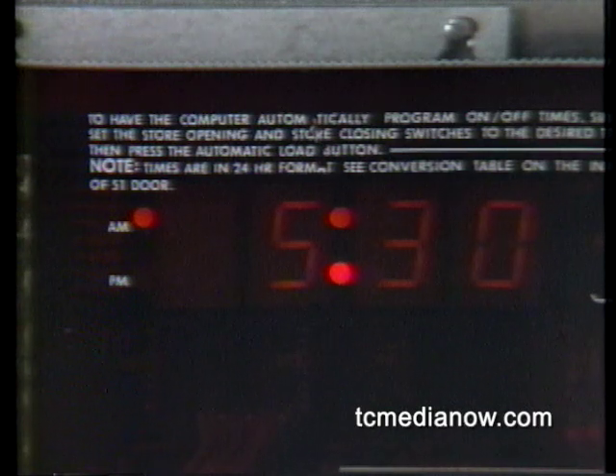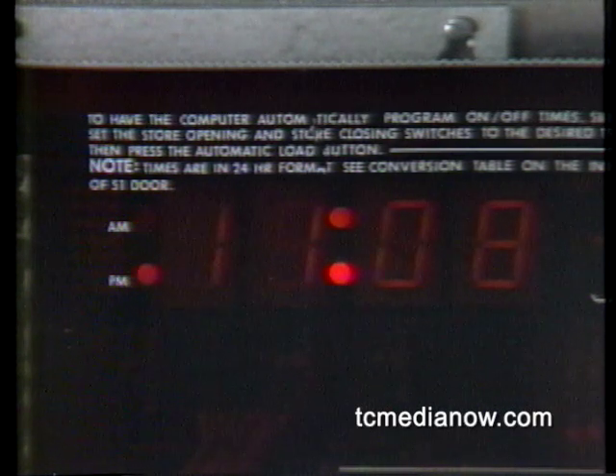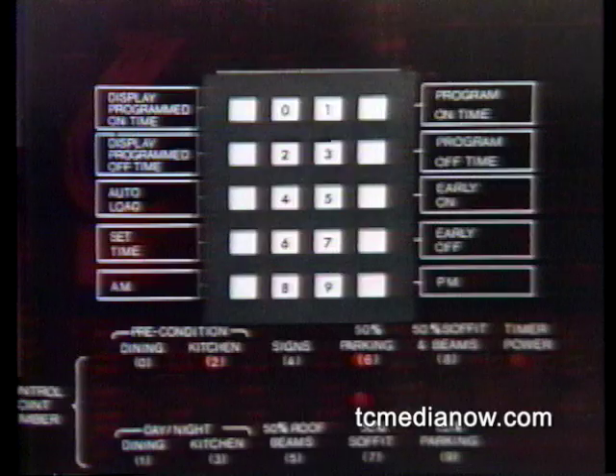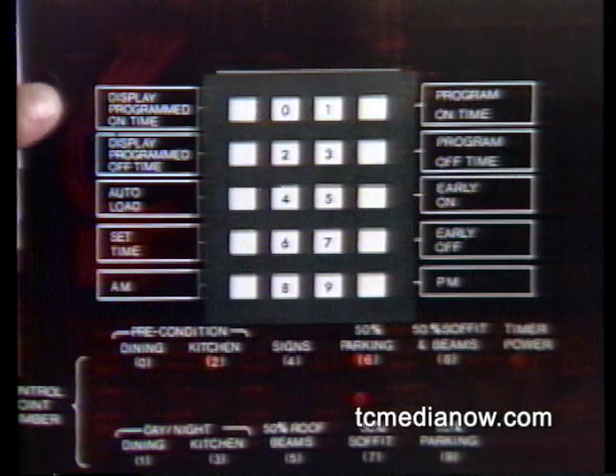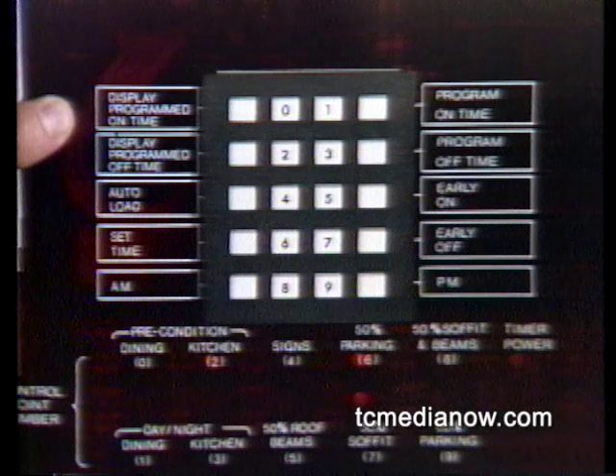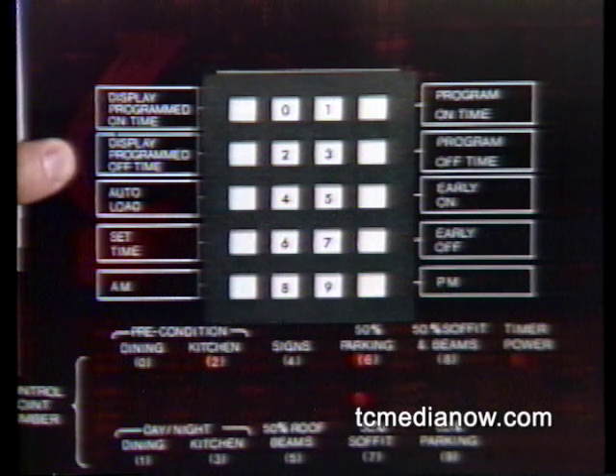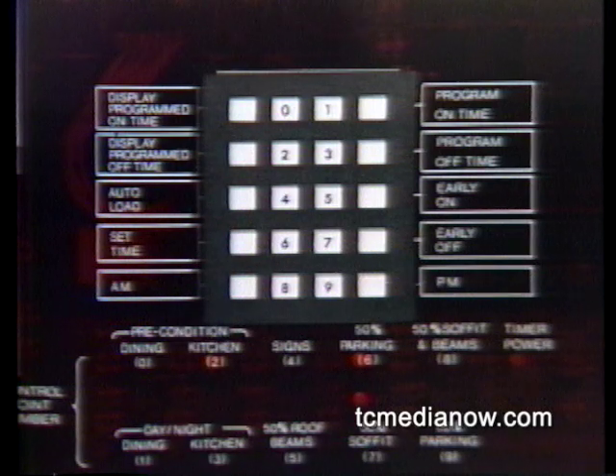Notice that the time you have just now entered shows on the clock, so you can verify you've made the right entry. After 8 seconds, the clock will reset to display the correct time of day. To review program time cues again, simply press the Display Programmed On Time button or the Display Programmed Off Time button and the number of the control point you wish to review. Display Programmed On Time, Control Point 2. Now the clock displays the time cue entered in the example we have just seen.